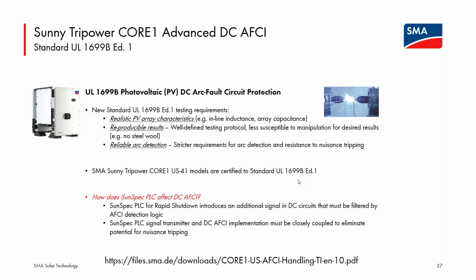Great. Hardwired communication options are ideal, but do the CORE1 inverters offer wireless communication options? Existing project with existing power conduits, but not the communication conduits. Carport arrays, parking lot has already been paved. It pains me to say yes, there is Wi-Fi built into the CORE1s. And the reason it pains me is because obviously you're going to then have lots of metal lids on the CORE1 carports. You're going to have lots of metal stuff all around this device. The Wi-Fi functionality is there in the CORE1s. It is a 2.4 gigahertz Wi-Fi channel only, but it has the ability, yes, to communicate via Wi-Fi built in.